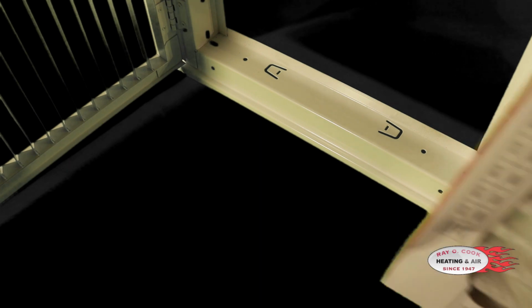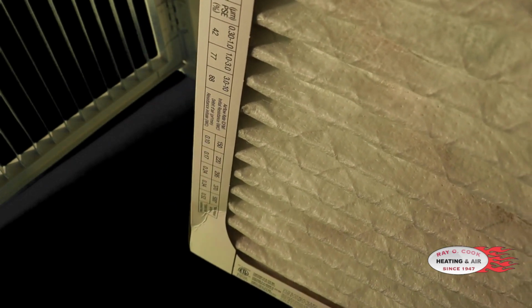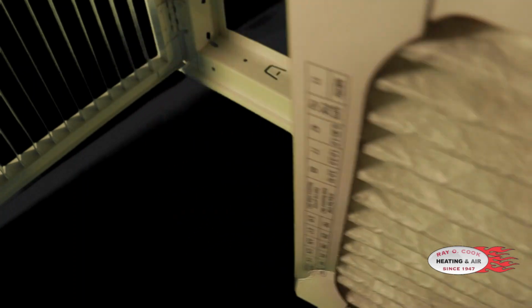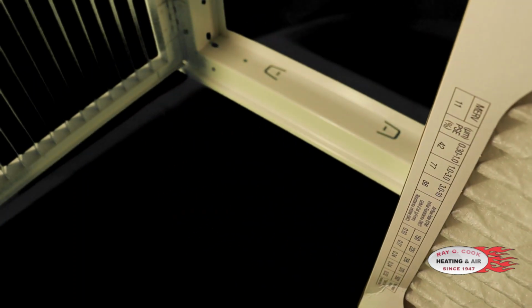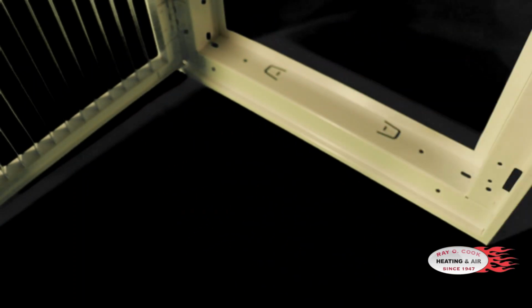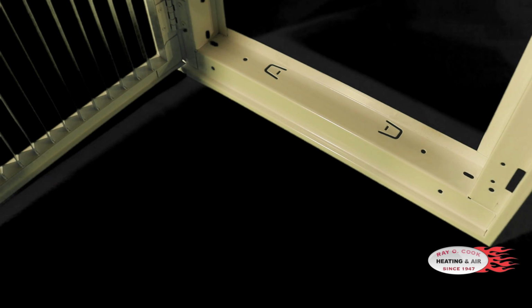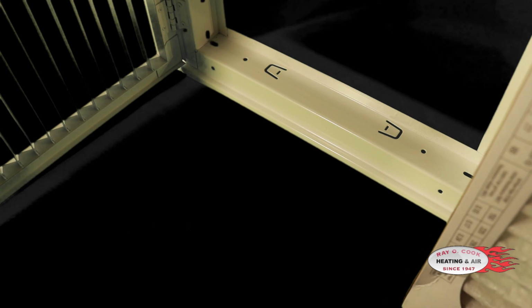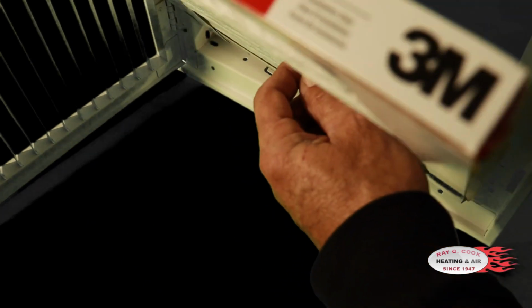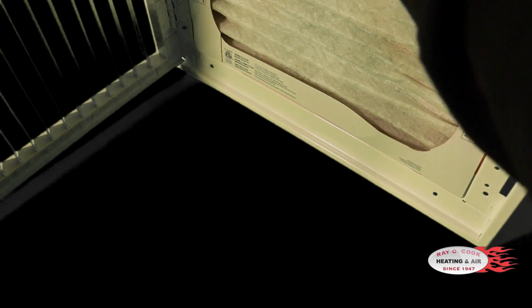And for instance, if we're putting in a MERV 11 filter, but it's too restrictive for our airflow, not only do we not get the flow to our equipment so that it works correctly, we get other unintended consequences. So when we put this filter in, if it is way too restrictive on our fan, that fan is going to get its air wherever it can.